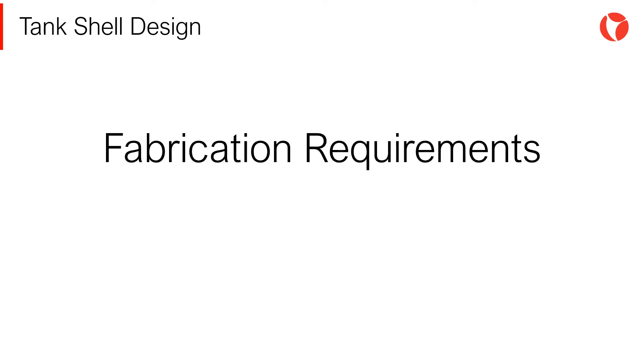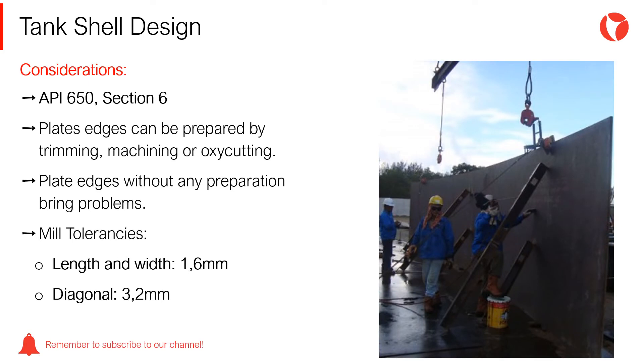To ensure that a storage tank meets the design requirements, it is necessary to follow certain aspects during the fabrication of the tank. For adequate tank fabrication, plates with prepared edges must be used according to the type of welding to be made. Plates should not be welded as they come from the rolling process, as this could lead to problems due to incomplete fusion of the weld. The API 650 code establishes the allowable dimensional tolerances for the plates used for the tank shell, being plus or minus 1.6 millimeters for the length and width of the sheets.